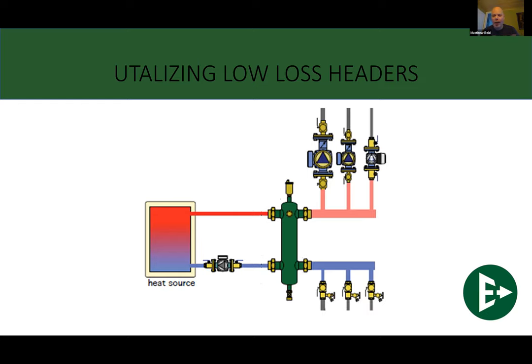Now, if you're doing a re-and-re, absolutely you want to put one of these things in. You don't know what's behind the drywall. You have no idea. Anything could be back there. Maybe that system pump that was there was drastically over or under sized. We have no idea. But by doing a low-loss header, we're making the boiler its own specific system, and then the heating side is its own specific system. So as opposed to the homeowner calling you and saying your boiler that you just put in is broken, you can go there and see that the boiler's fine. There's no issues there. It's a system issue. And on a re-and-re, that's quite important because it shows your product is fine. The system is the issue. And then for new installs, it helps you diagnose what may have gone wrong with your system as a whole.